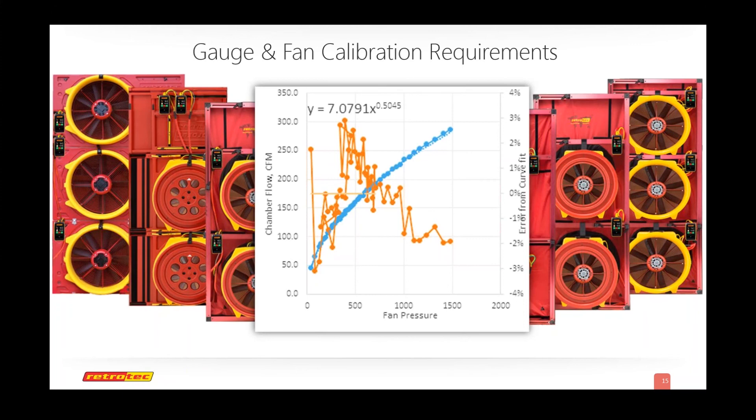Colin adds: better to think about it in percentages rather than CFM. A 1% error in the gauge translates to about a 0.5% error in the flow measurement. Even a 10% gauge error is only about a 4% difference in flow. The best flow measurement devices available cost thousands of dollars and are lucky to get within half a percent. Gauge measurement is easy — Retrotec gauges are always within a percent, probably most of the time within 0.1%. It's really the fan itself that is the source of error, which is why they've been focusing on fan accuracy.